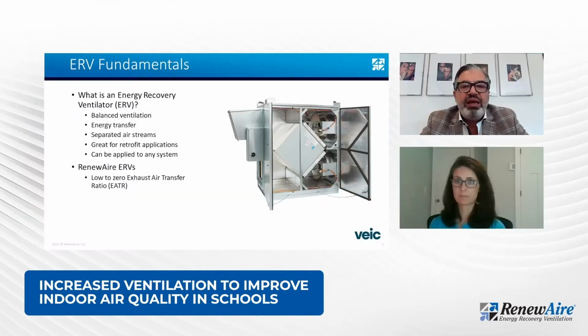When we talk about outdoor air, it has such a huge impact on an HVAC system, whether it's on the roof or whether it's a terminal unit. Especially if you're going to increase the amount of outdoor air, that impact can be quite dramatic. So we use energy recovery ventilation systems to temper the outdoor air that's coming in with the energy that we would be throwing out from the exhaust air.